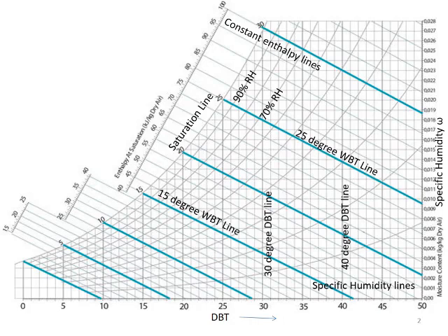For example, from 15 to 25, it is divided into 5 equal parts, means each is 2: 15, next 17, 19, 21, 23 and 25. Whereas 25 to 40, a 15 gap is there and it is divided into 1, 2, 3, 4, 5, 6 parts, so 15 by 6. That is how you have to read. So these lines are the constant enthalpy lines.